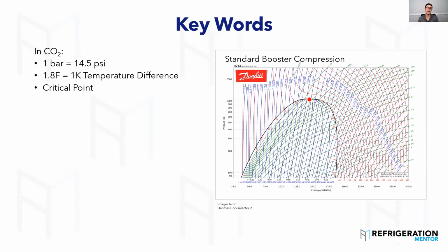But now with CO2, it has a really low critical point. And you'll see it at 87.8 Fahrenheit or 31 degrees Celsius. So when you're above that, you're in what we call our transcritical or supercritical zone. And that would be, if you can see my cursor right here, right up here. So when you're up here, that means you're in transcritical mode or you're in that supercritical fluid zone. So it's not really a liquid, it's not a vapor, it's like a fluid.